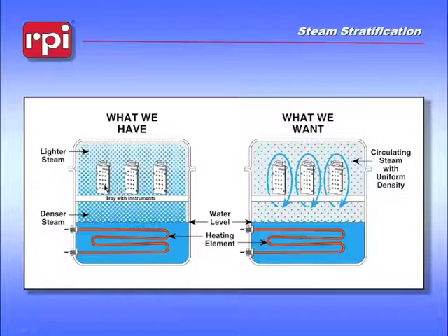You have no circulation of steam within the chamber. Now if you're only doing scissors and nail clippers, that's okay — there are no little entries that need steam exposure, and this will work very well for those instruments. But anything more complicated, we need to be able to actually circulate the steam within the packs, move it around, and get it to the point where it gets good exposure within all of the little pits and containers and chambers within the instruments.